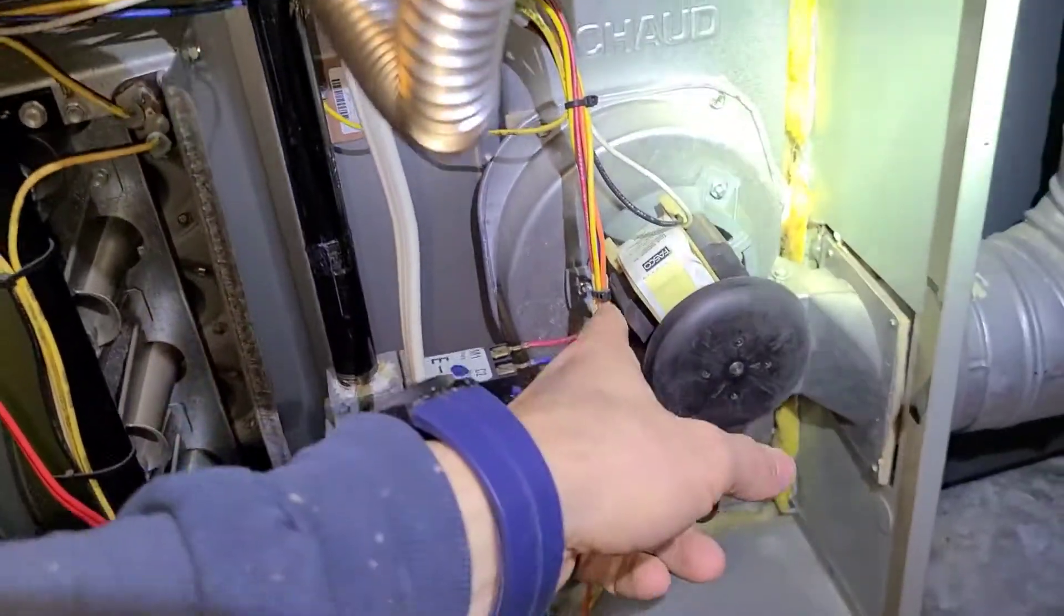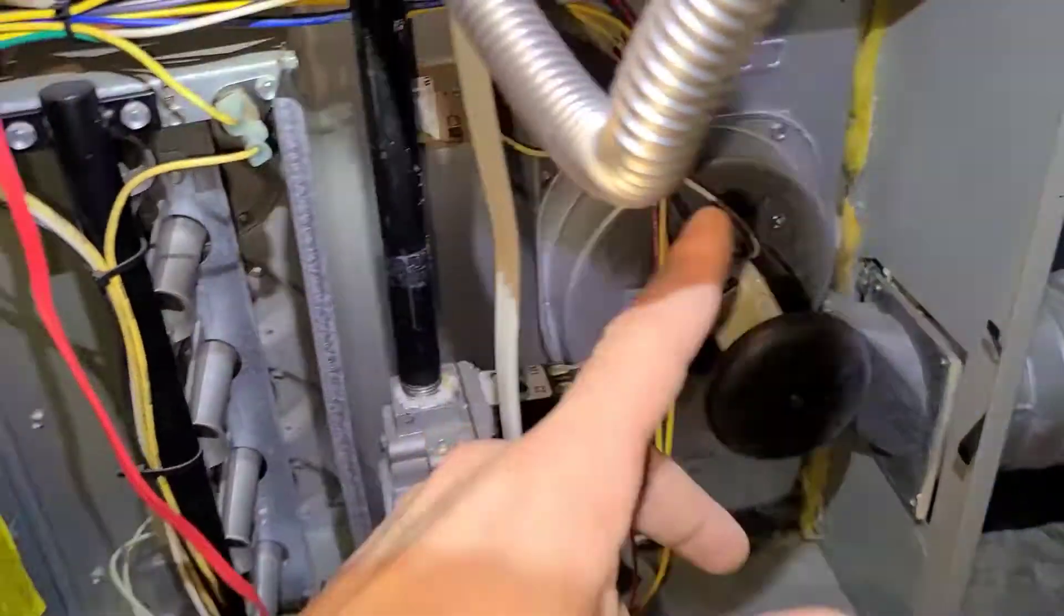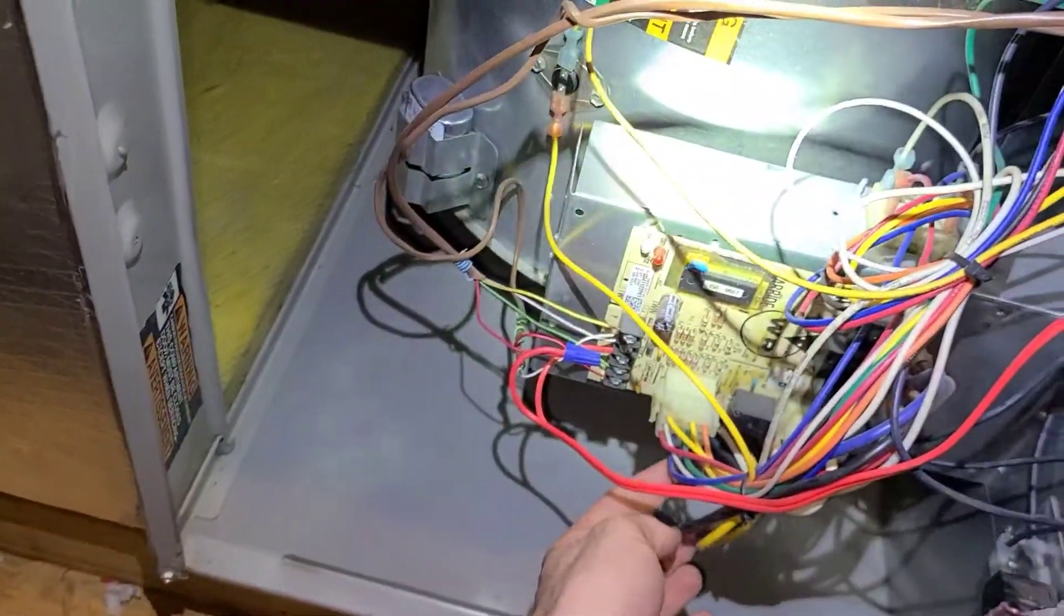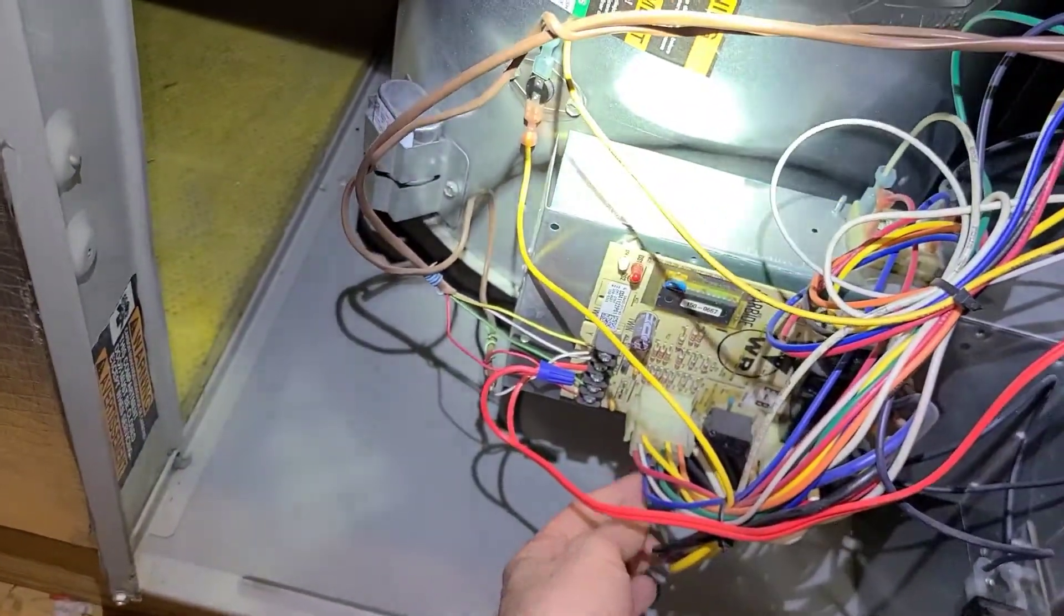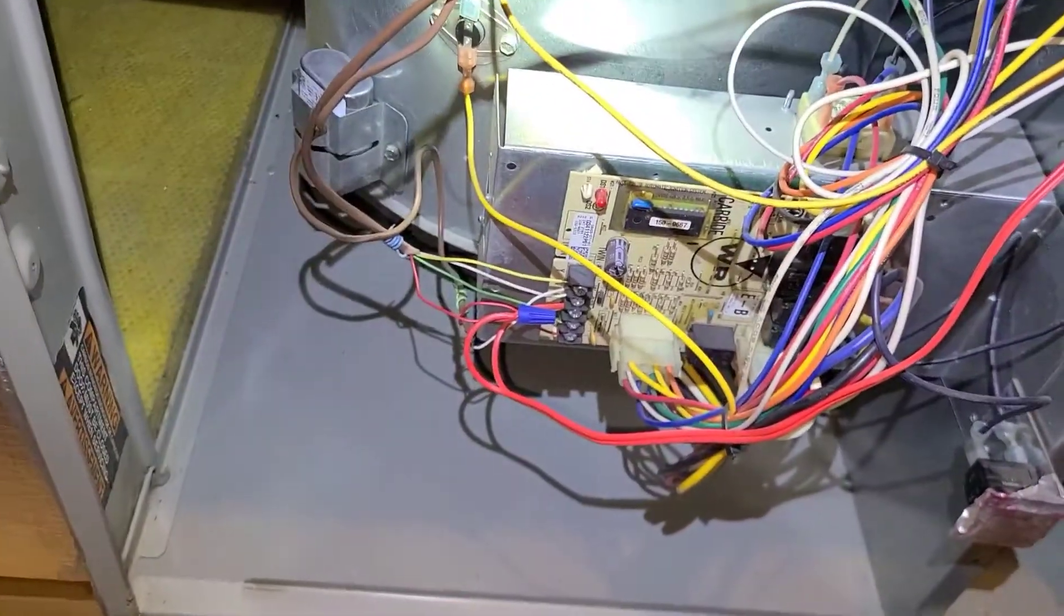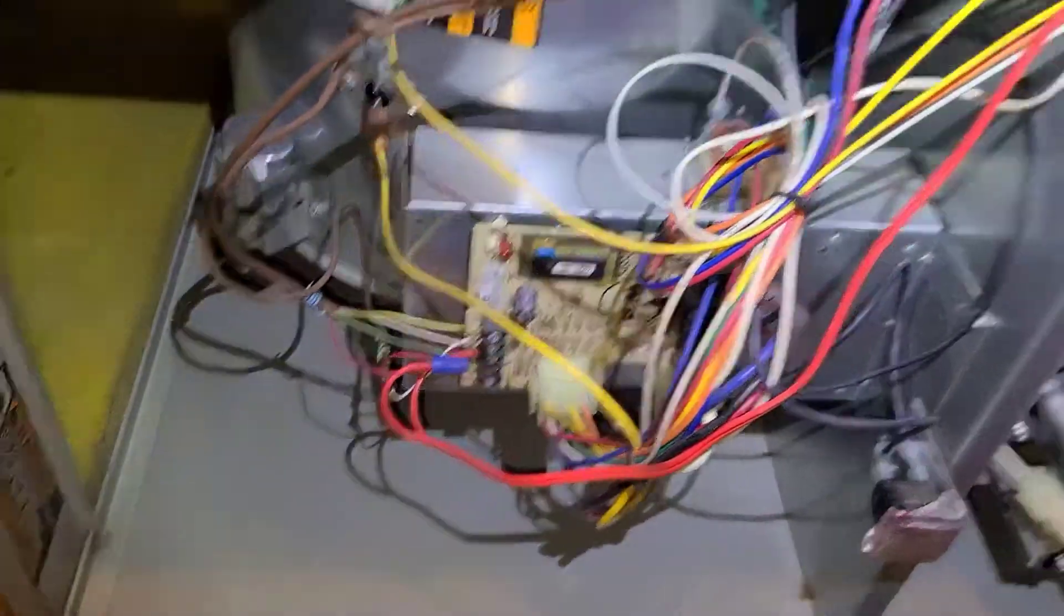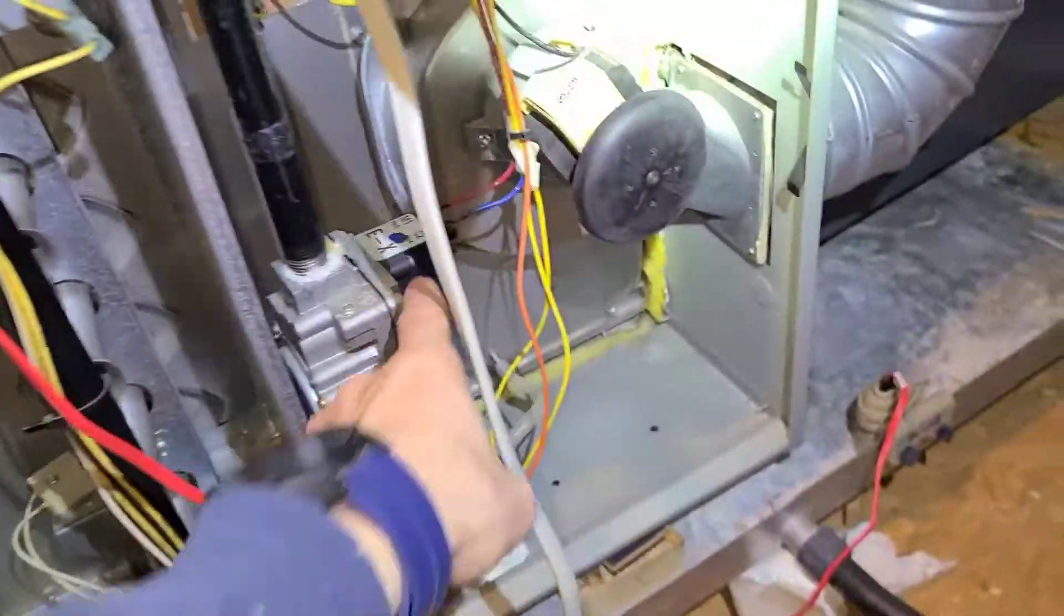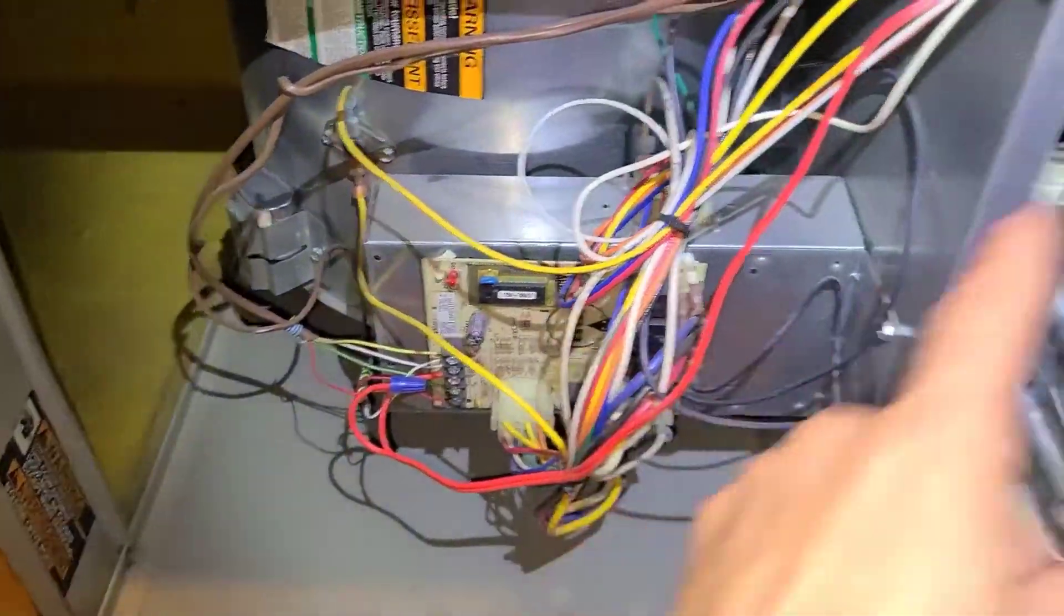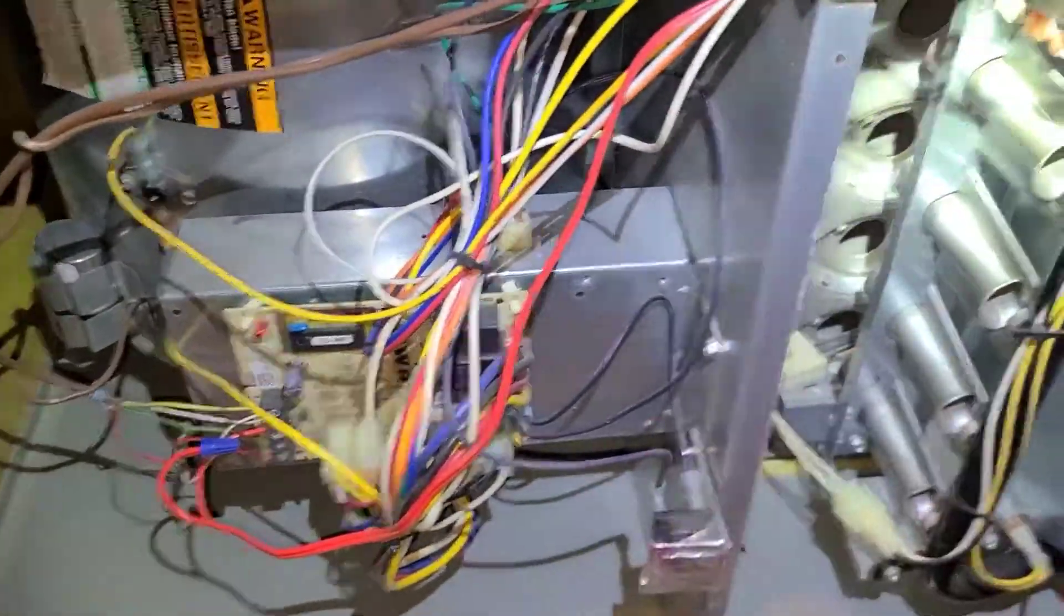I traced the voltage back to the control board over here to this prong connector. I am getting 24 volts there, but I'm not getting it here, showing that the control board is not sending the 24-volt signal to the gas valve.